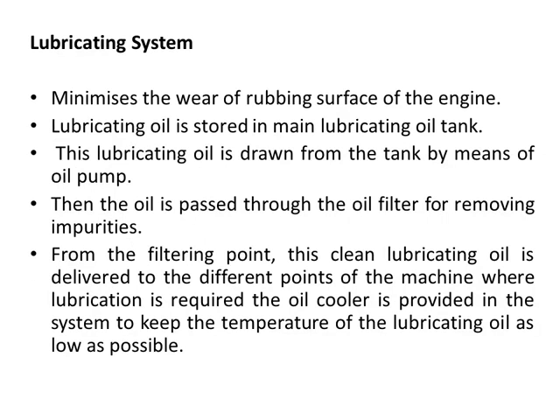The lubrication system minimizes the wearing of rubbing surfaces of the engine. Lubricating oil is stored in a lubricating oil tank, drawn by an oil pump, and passed through an oil filter to remove impurities. This clean lubricating oil is delivered to the different parts of the machine where lubrication is required. An oil cooler is provided in this system to keep the temperature of the lubricating oil as low as possible.